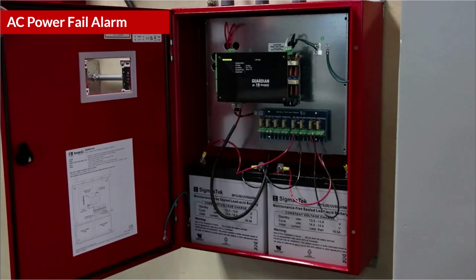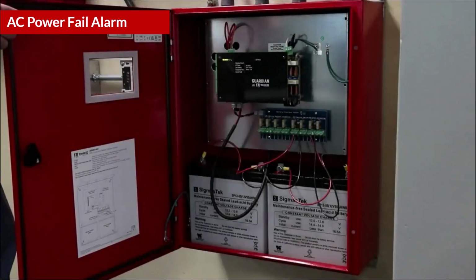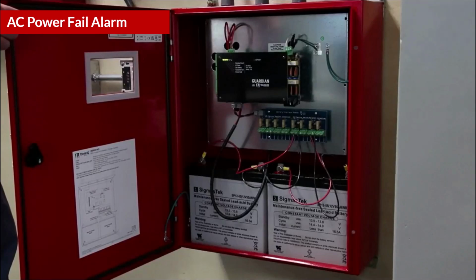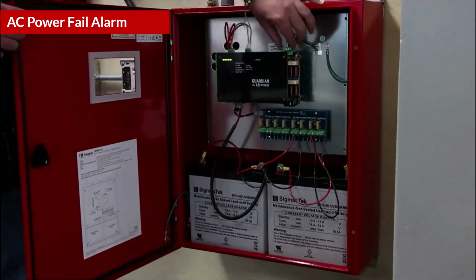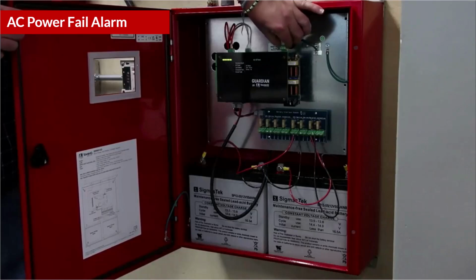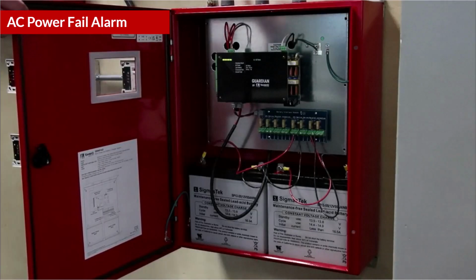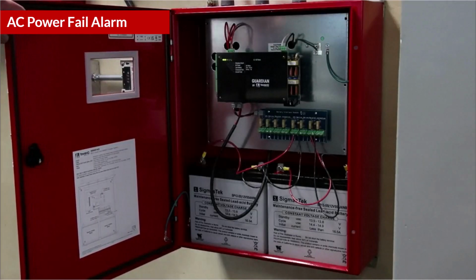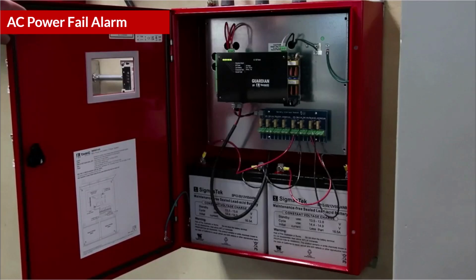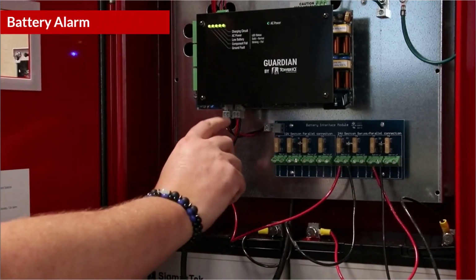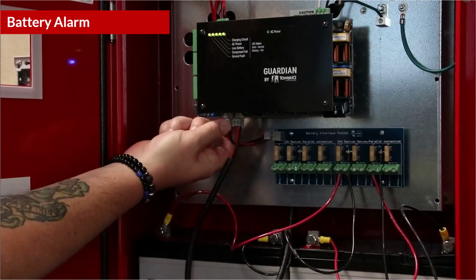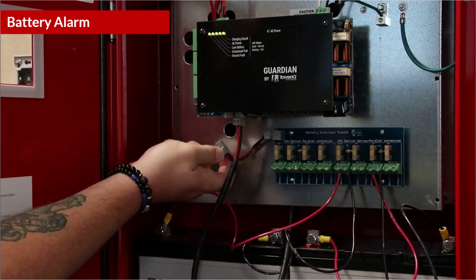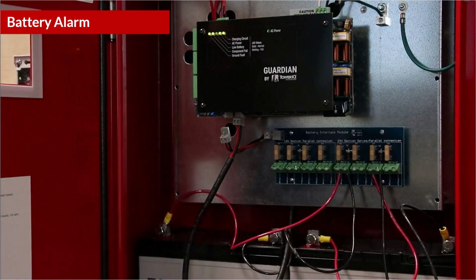Activating the loss of AC power alarm is as simple as disconnecting the AC cable's supply power to the battery backup, or BBU. Once the alarm triggers, the AC cable can be reconnected and the system should return to normal. To activate the low battery alarm, you must eliminate AC power and allow the batteries to deplete to 70% or less before the alarm will activate.